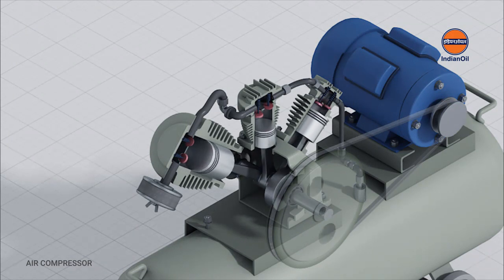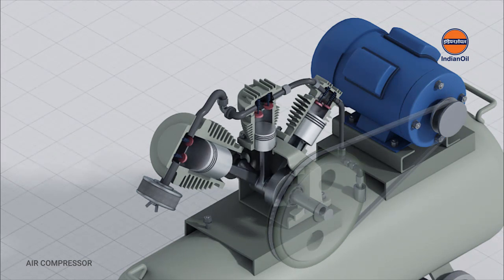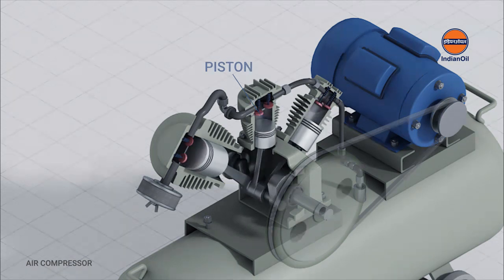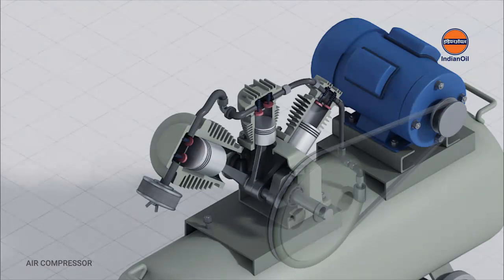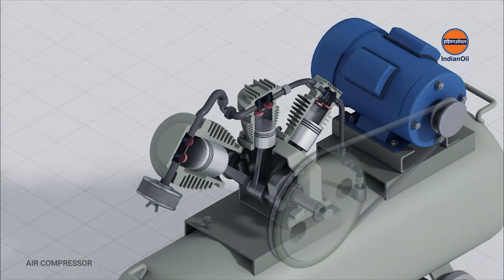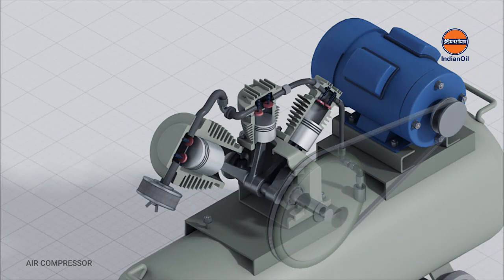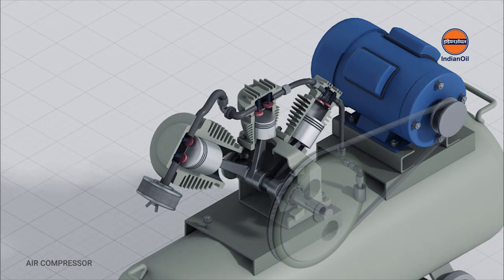The function of multiple cylinders in reciprocating compressors is also to cool the temperature of the machine during its compression cycle, which tends to generate heat. Piston — the mode of operation of the compressor greatly relies on the piston, as it is the component that actually compresses air. It also moves the energy from the crank case to the gas contained in the cylinder. In between the piston and cylinder walls, this component is usually covered with piston rings. Its movement brings about the suction and compression of the air.